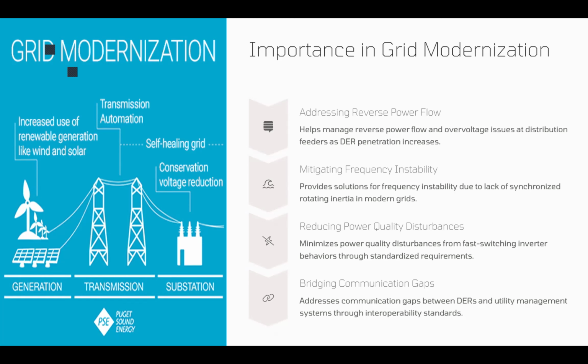Now, this standard comes in and mandates compliance with the harmonic limits defined in the complementary standard IEEE 519. It also requires the DERs to maintain voltage flicker within certain permissible limits, and makes a rule that the DER should operate in a certain range for the power factor. That way, we can make sure we have a level of power quality that will not jeopardize our grid stability.